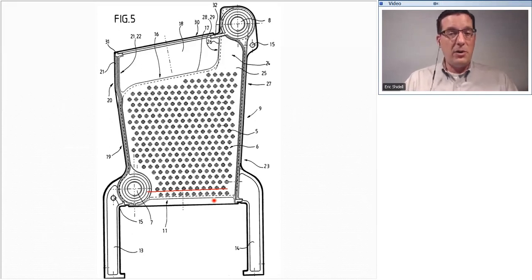Originally, boilers were all steam boilers, and they did boil. But then somebody got the bright idea and said, hey, maybe we don't necessarily need steam. Maybe we just circulate warm water. That'll work just as well. And the hot water boiler was developed. And that's what we're talking about here: hot water boilers. When that water begins to boil, little steam pockets will erupt suddenly out of that mud into the water, and that's what's creating the popping sound. Now, that isn't necessarily a hazard. It's not necessarily dangerous. But what is a problem is that it's not giving a very effective transfer of heat into the water.